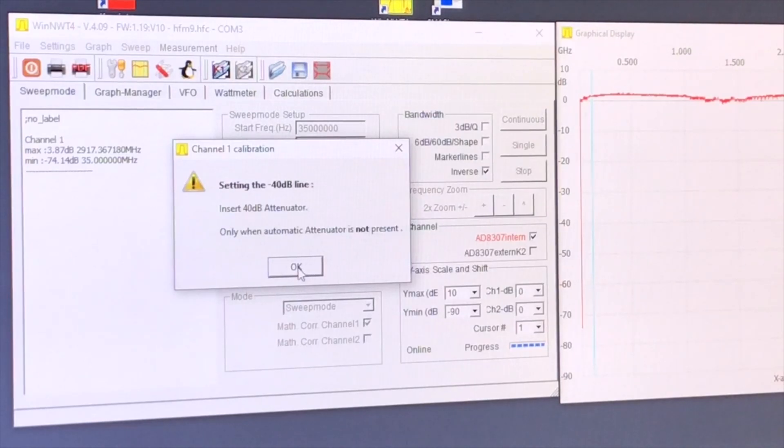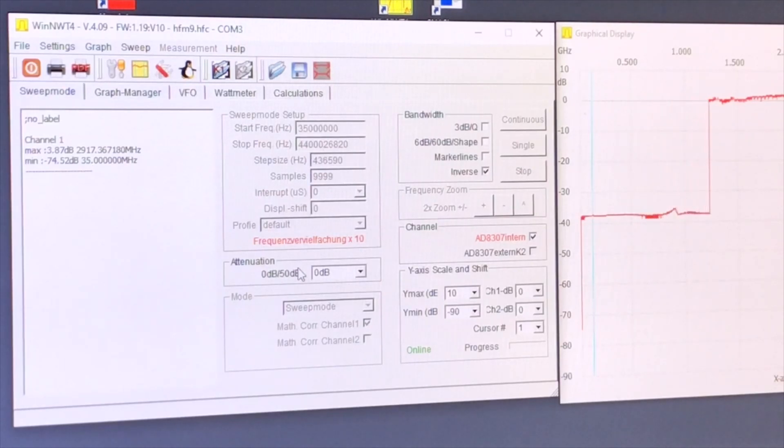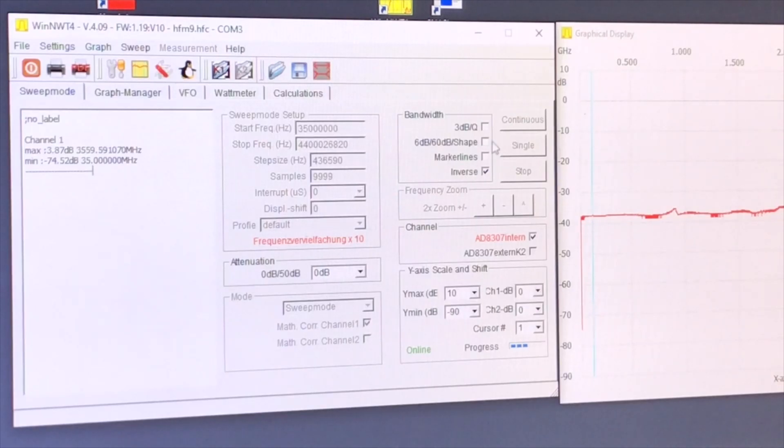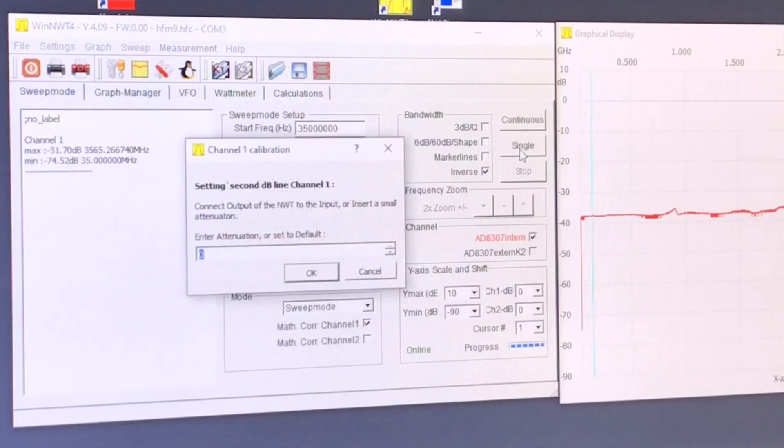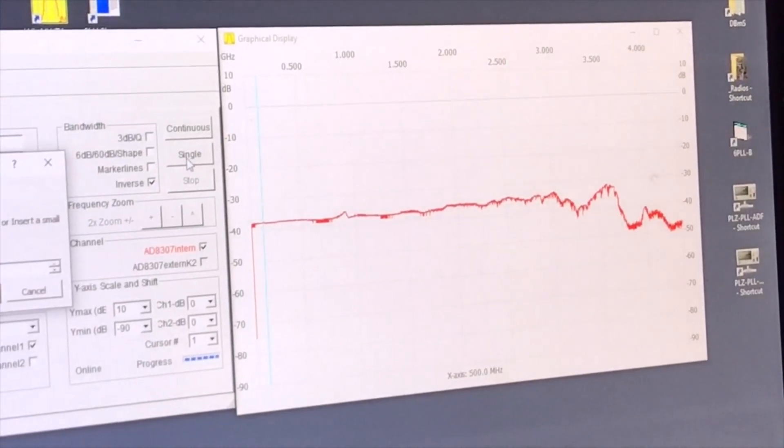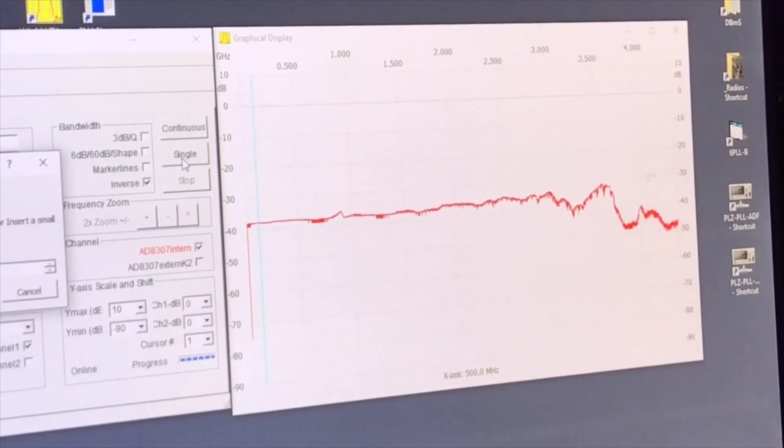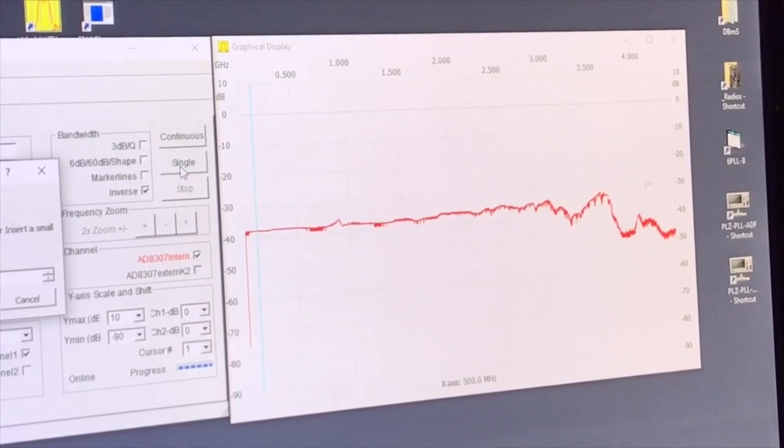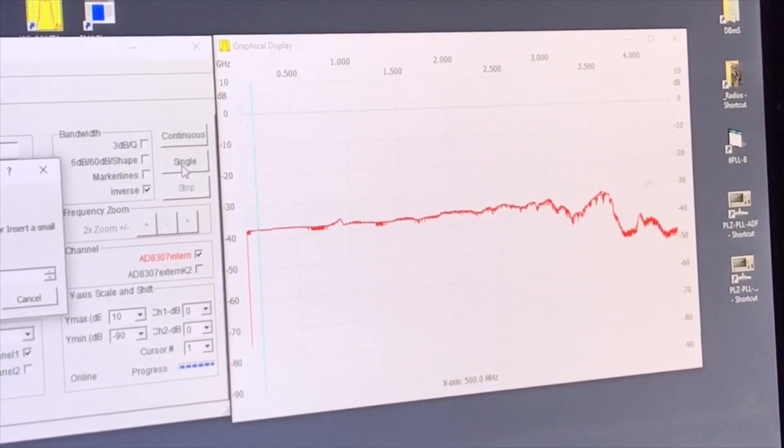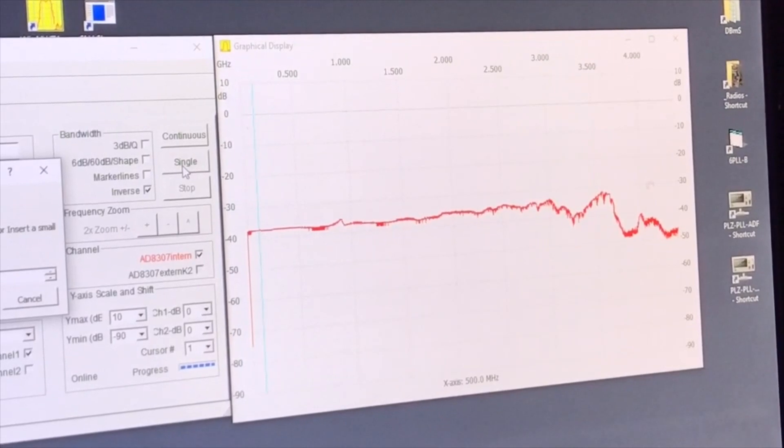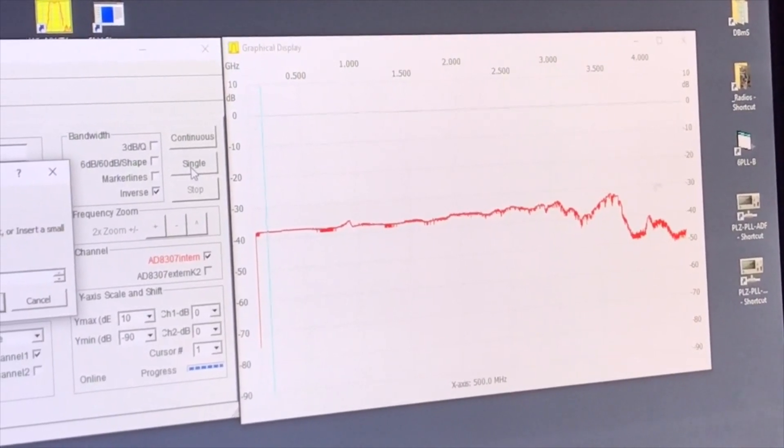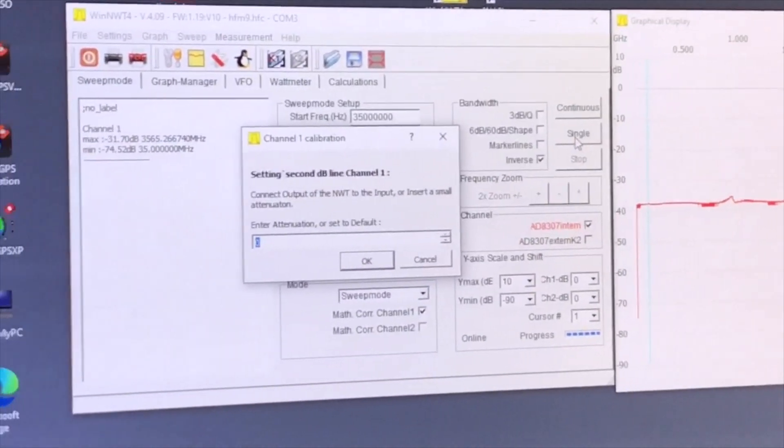Sometimes it gives an error and then it says I cannot communicate with the spectrum analyzer. But what you do then, you just wait 10 seconds and then you just put the button here for single. And then it just proceeds with the calibration. First, we're going to look at the result. As you can see, it is not that straight. That could be the tracking generator or that could be the analyzer itself. But we're just going to try to normalize that.